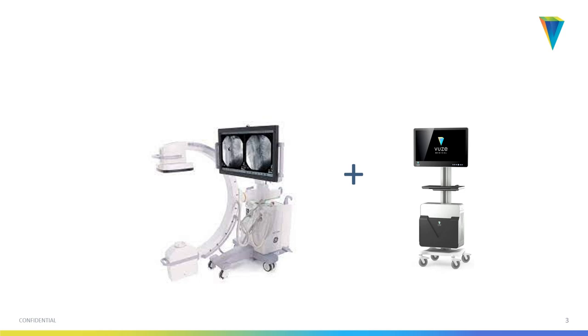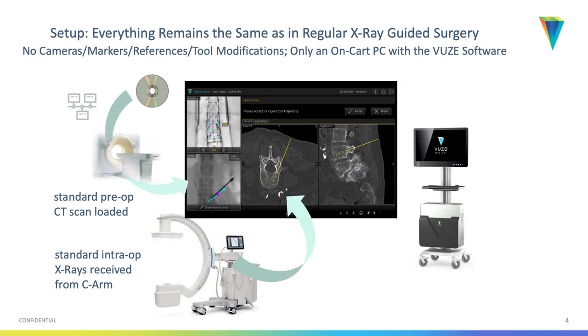All there is in the cart is an off-the-shelf PC and an isolation transformer. By now we have the system running on a laptop as well. A mobile C-arm and the VUZE PC running the VUZE software — that's really the setup. The VUZE screen merges the visual information from the x-ray and the CT into an integrated 2D/3D world. The pre-op CT is loaded, be it via DVD or network.